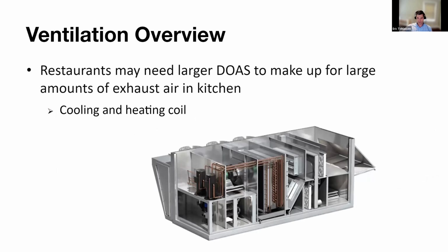So here's an example of a DOAS system. You can see it has its own separate cooling and heating coil. And one thing to keep in mind is for restaurants may need larger DOAS systems to make up for the amounts of exhaust air in the kitchen, right? So you want to keep your kitchen as a negative space, so you're exhausting a lot of air, making sure the smells don't get out to the restaurant. So just something to keep in mind, that you might require larger DOAS systems.